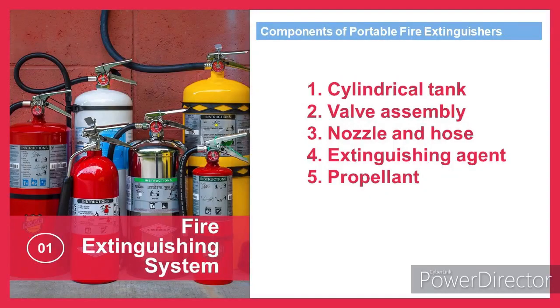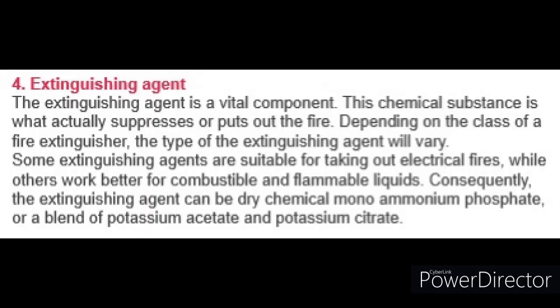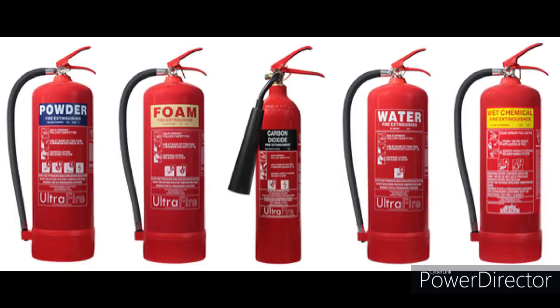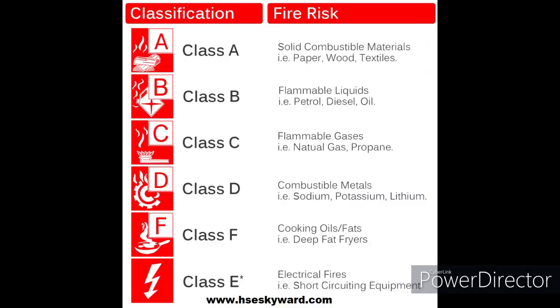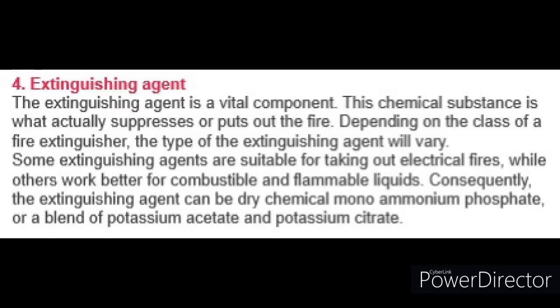Fourth component is the extinguishing agent. The extinguishing agent is a vital component. This chemical substance is what actually suppresses or puts out the fire. Depending on the class of a fire extinguisher, the type of the extinguishing agent will vary. Some extinguishing agents are suitable for taking out electrical fires, while others work better for combustible and flammable liquids. Consequently, the extinguishing agent can be dry chemical monoammonium phosphate, or a blend of potassium acetate and potassium citrate.